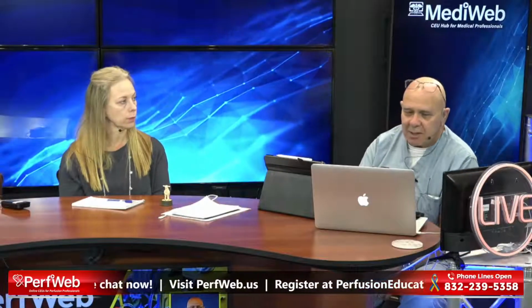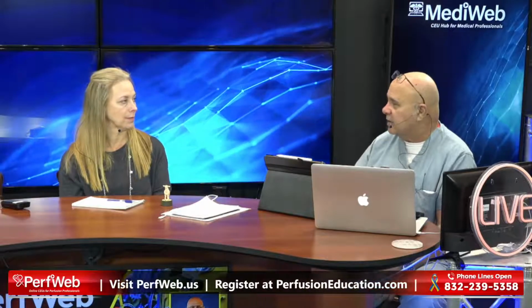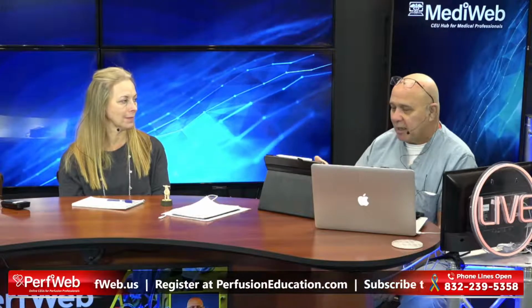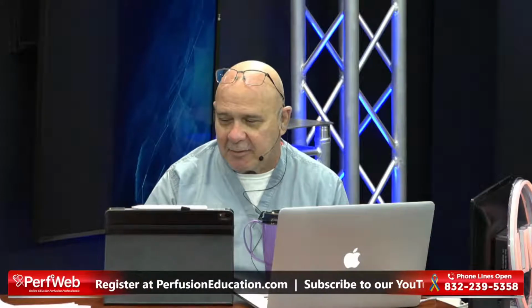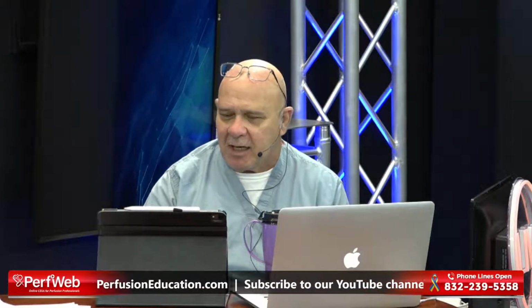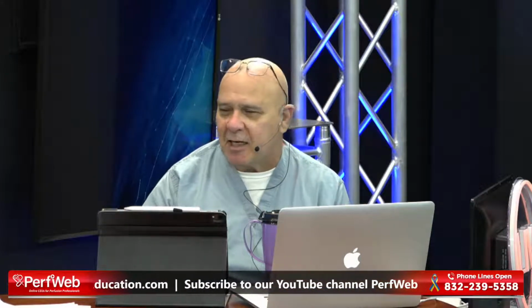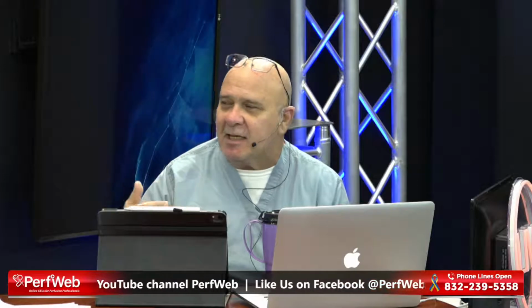Well, I mean, one time I didn't do what I normally do. I skipped a step. Usually nothing ever goes right when you do that. I went on bypass. I opened the venous line up and I opened the arterial line up, and I didn't even wait. It happened immediately, and I realized I hadn't hooked my gas lines up yet. The crystalloid was still coming down when I realized that was it, and I got it connected really fast.